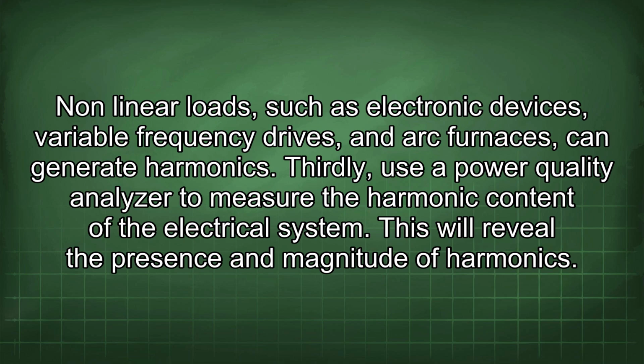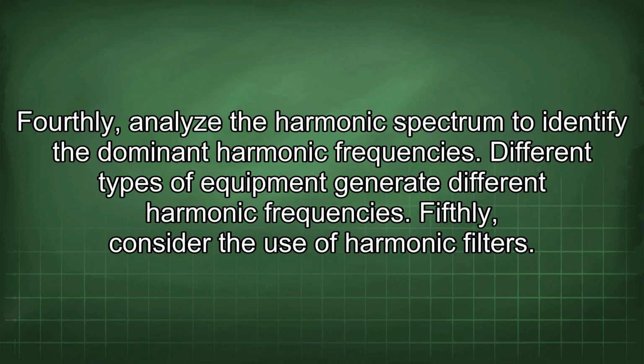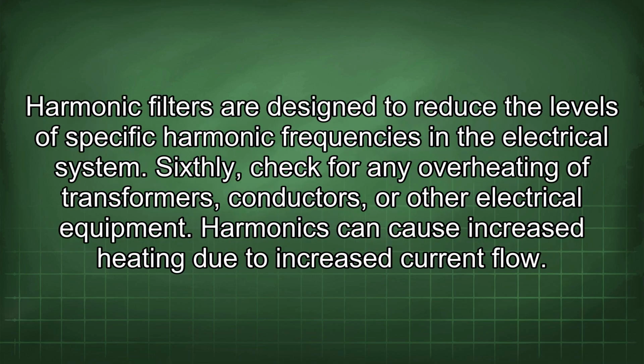Thirdly, use a power quality analyzer to measure the harmonic content of the electrical system. This will reveal the presence and magnitude of harmonics. Fourthly, analyze the harmonic spectrum to identify the dominant harmonic frequencies. Different types of equipment generate different harmonic frequencies. Fifthly, consider the use of harmonic filters. Harmonic filters are designed to reduce the levels of specific harmonic frequencies in the electrical system.